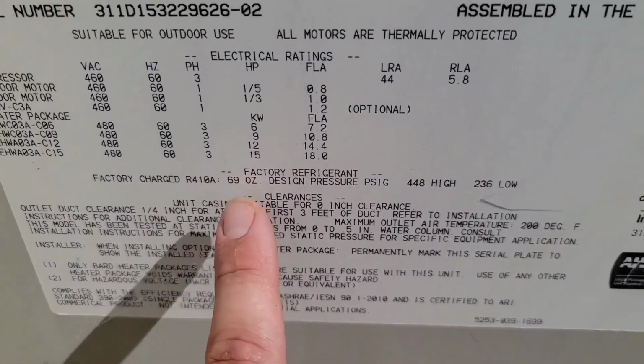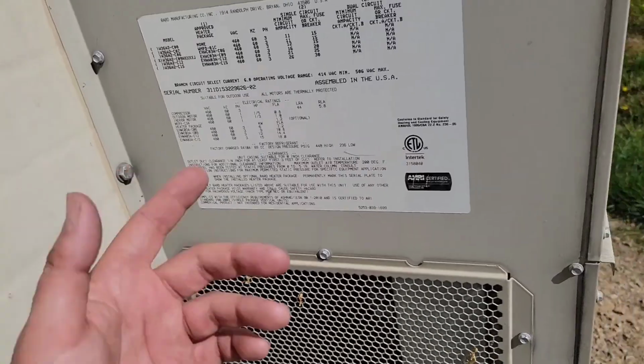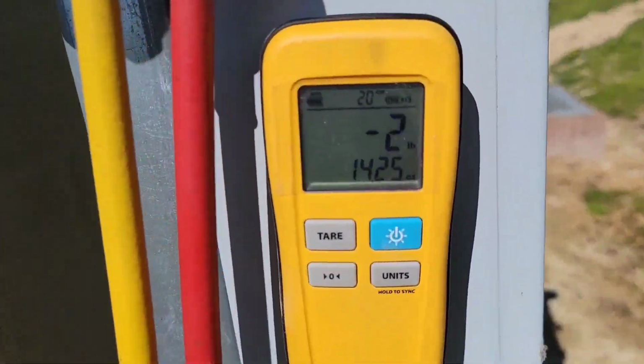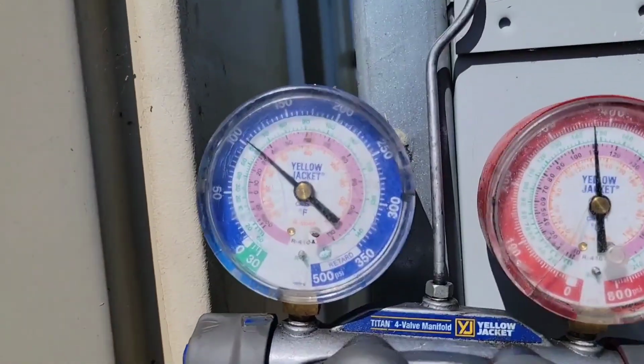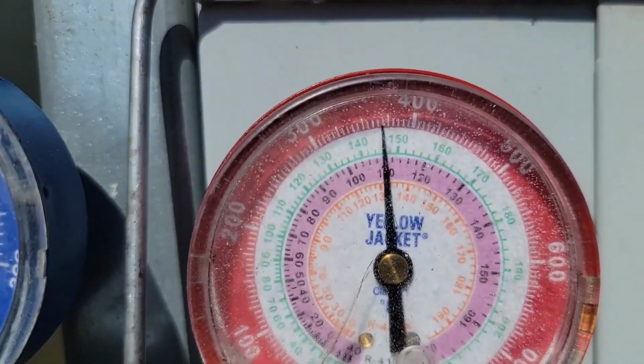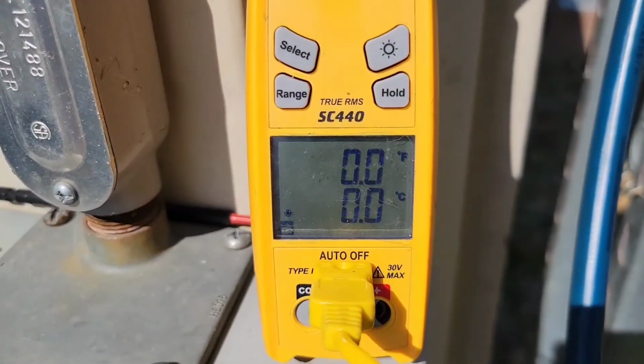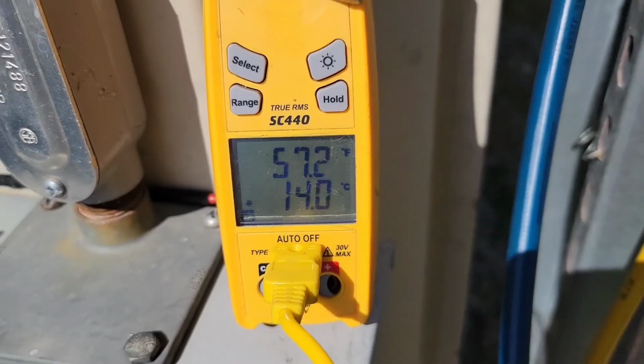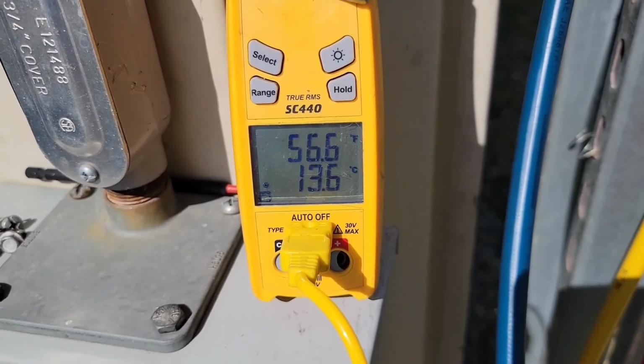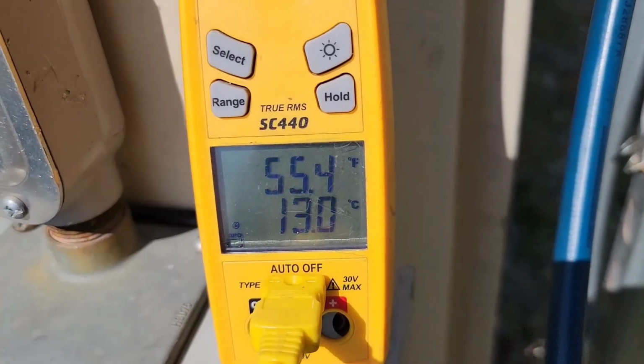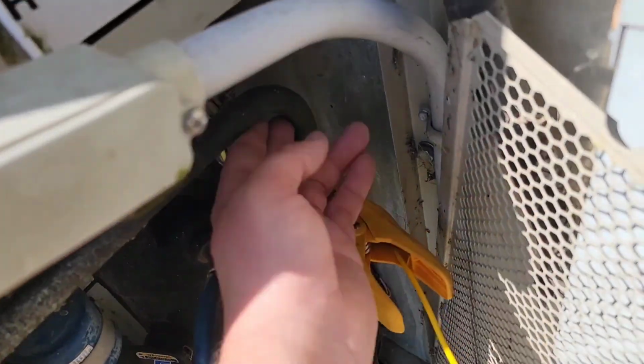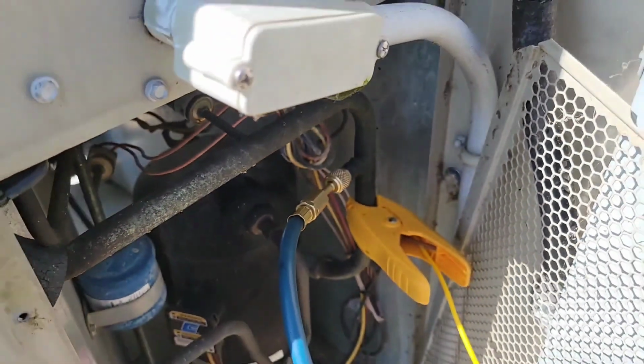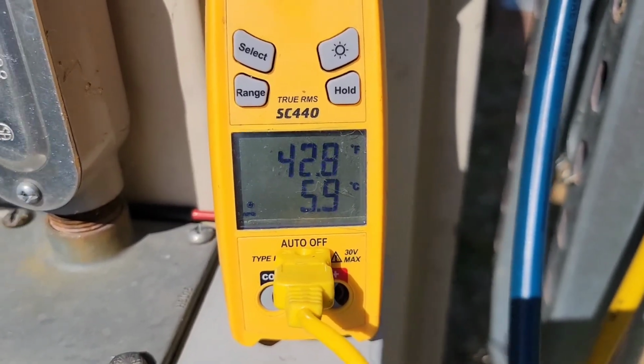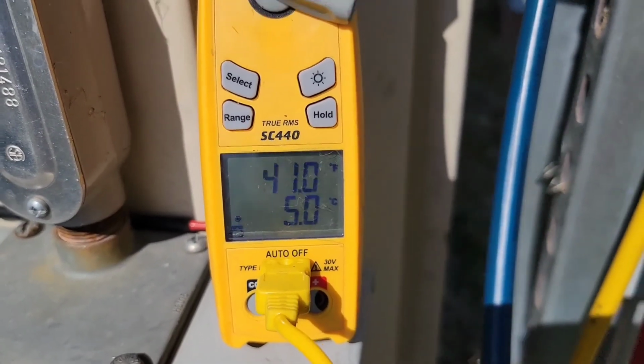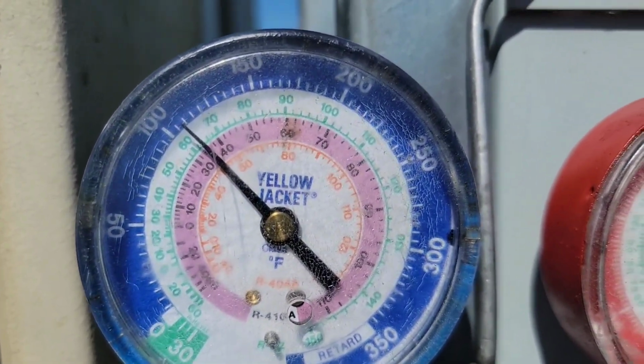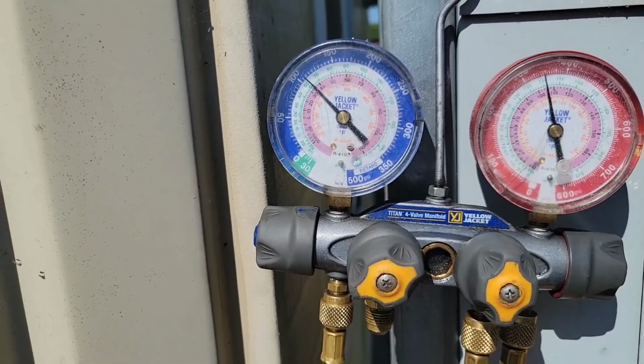Unit kicked back on. This unit only holds 69 ounces, so it's a little over 4 pounds. And we put 3 pounds in this thing, so it is leaking, definitely leaking bad. So we've got 105 and about 360. And what does my meter say? Okay, got a good suction temperature now. 57, 56. Okay, 55. Okay, so it's 54. So okay, we've hit the sweet spot. This line is nice and cool now. Oh wow, yeah, we've definitely hit the sweet spot. 41. Okay, excellent. So if we look at 41 and about 35, that's 6 degrees of superheat.